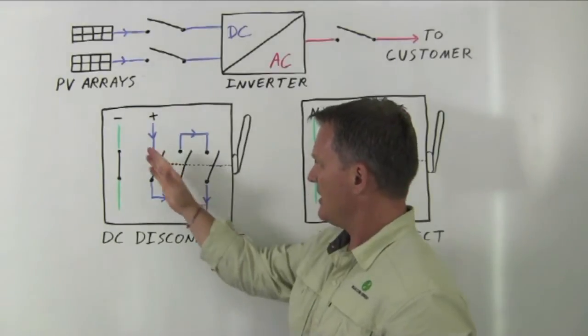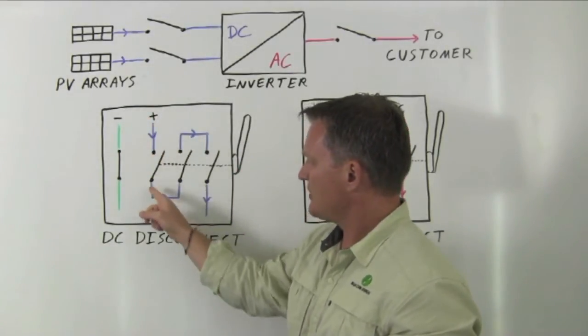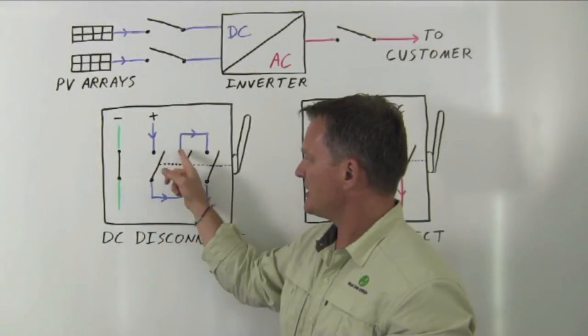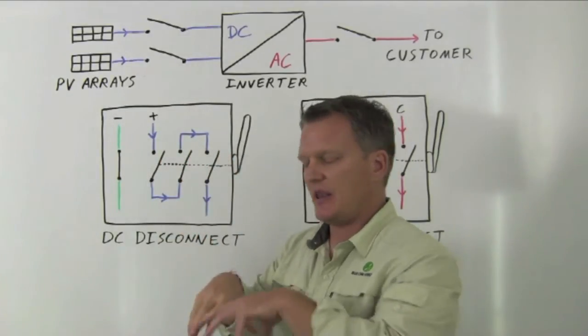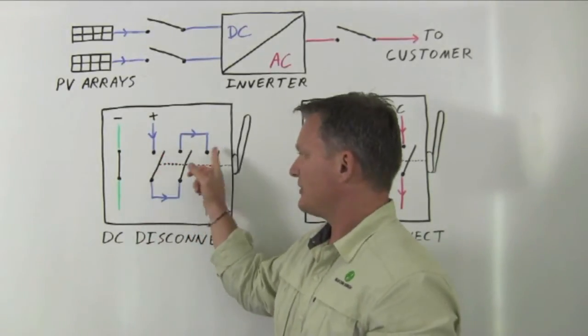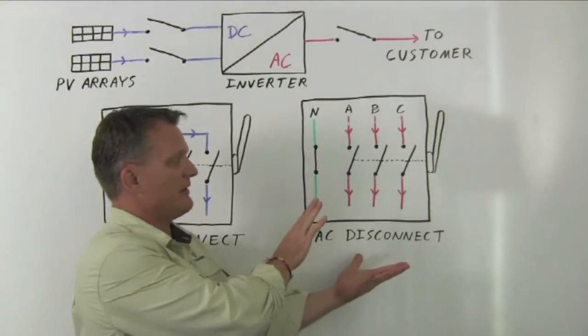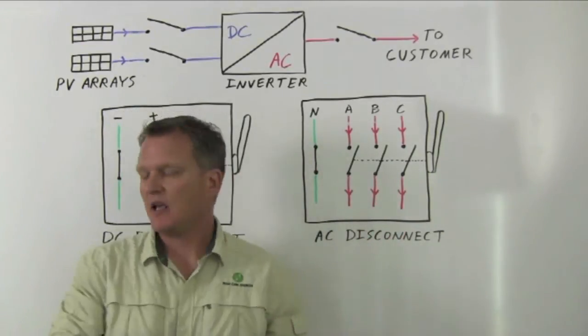But you have a single circuit going through here, and you basically increase that air gap—that air gap that's required to dissipate that arc—by a factor of three. This is how you can take a typical commercially available AC disconnect and use it in a DC disconnect application and still maintain its UL listings and still be safe.